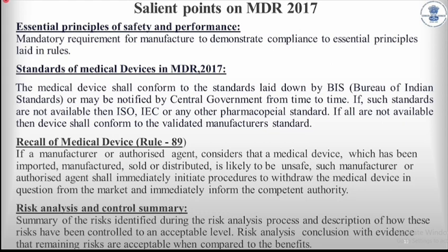Risk analysis and controls. As you all know, there are various levels of risk involved with the usage of every medical device, and the risk analysis and control summary is another key document wherein the risks associated with the devices are identified before the device is put in the market.